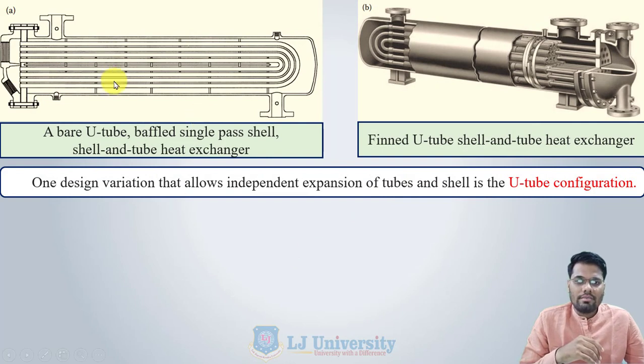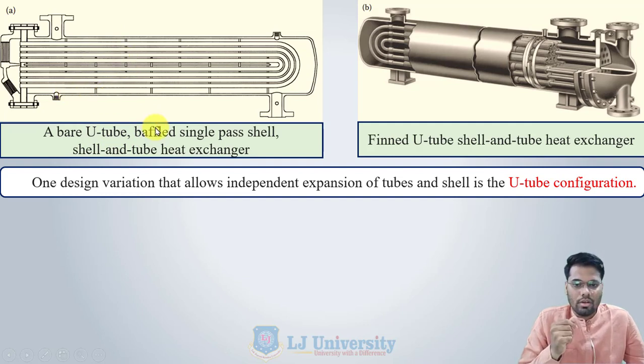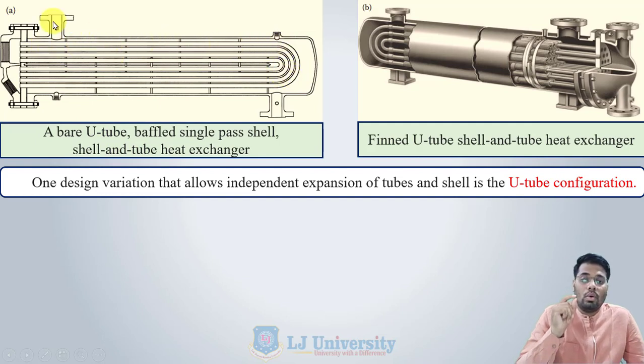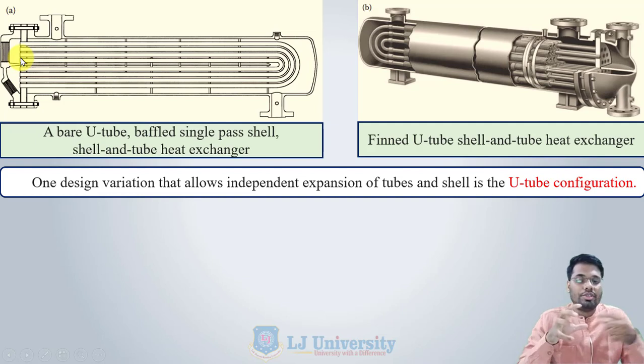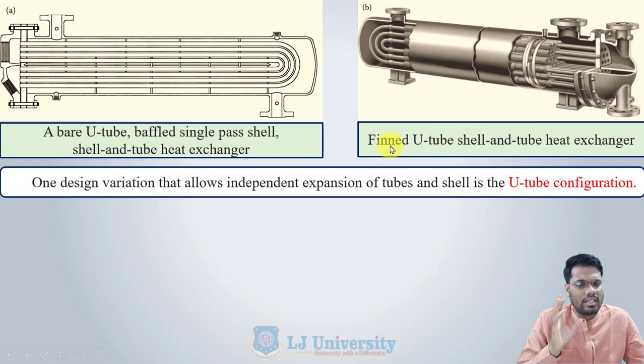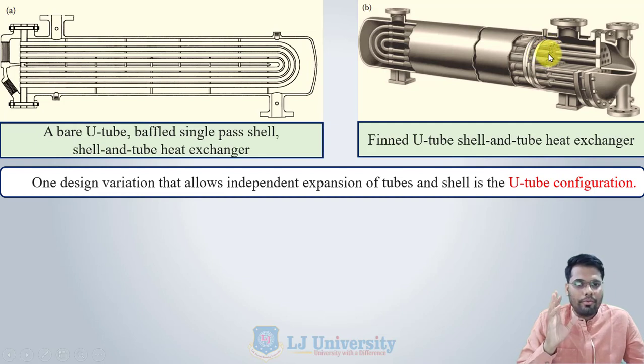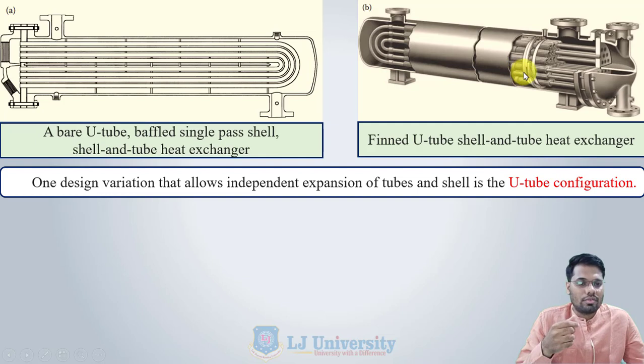The first type is a bare U-tube — 'bare' means there is no arrangement of extra surface or finned surface — in a single pass shell and tube heat exchanger. The U-tube starts and ends at the tube sheet, so only an even number of tubes are present. The second configuration is the same but with extended fin surfaces provided at the outer surface of the tube to enhance heat transfer.